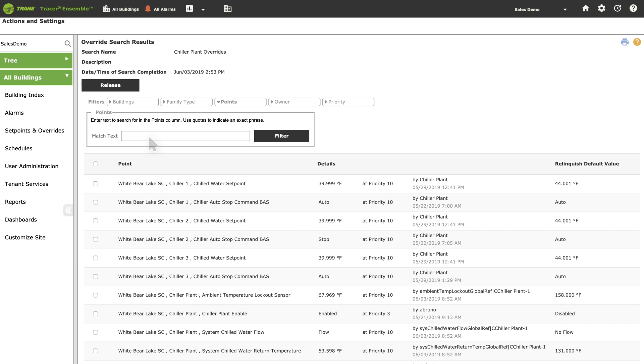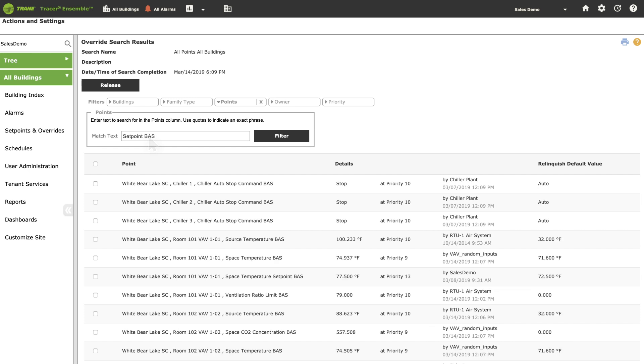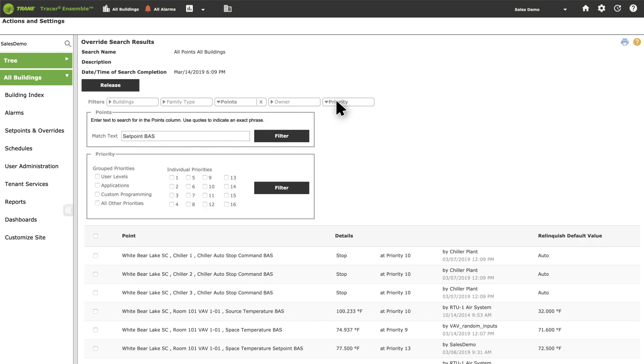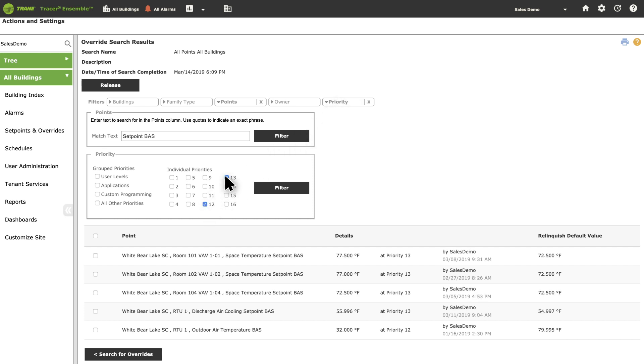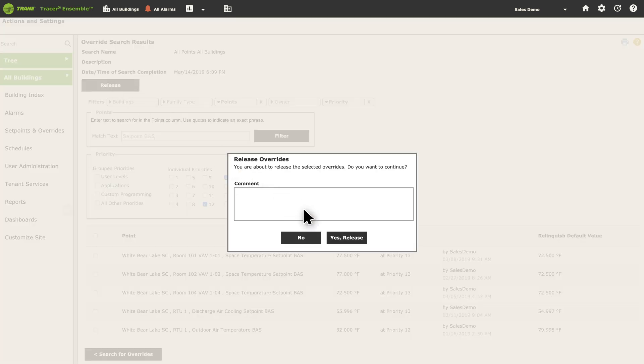Tracer Ensemble searches for system overrides and compiles them into a list. It clearly states the location of each override, identifies the person who performed it and at what level. More importantly, restoring optimal system settings is easy. Simply select all to release them with a single action.